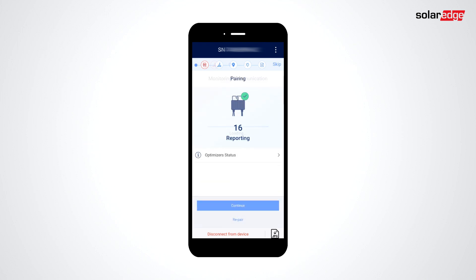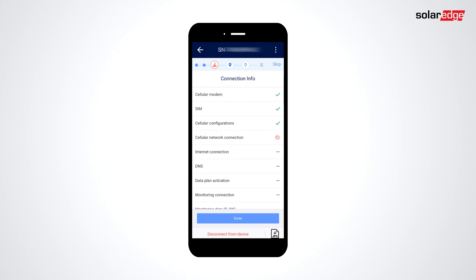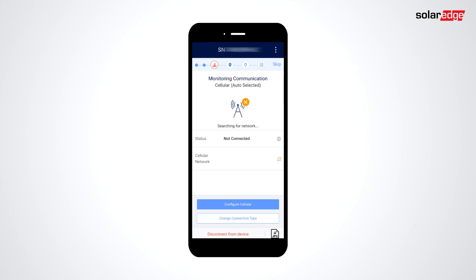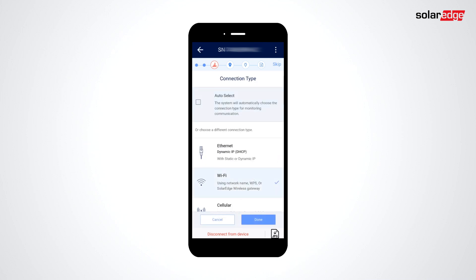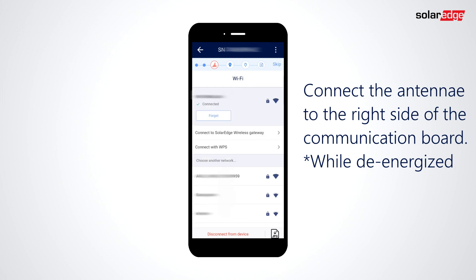Let's continue commissioning by setting Monitoring Communications. If you have a cellular plug-in, communications will automatically connect. To view the state of connection, you can click the status information icon. If you're not getting signal or would like to connect via Wi-Fi, click Change Connection Type. Select Wi-Fi, then select your network and enter a password. Note that a Wi-Fi antenna is required.